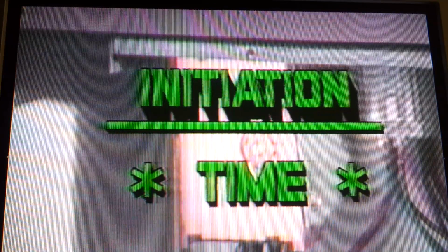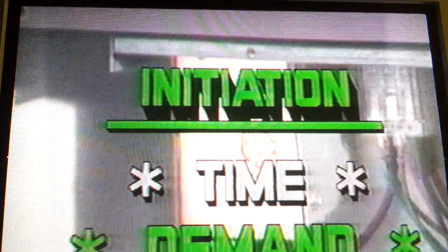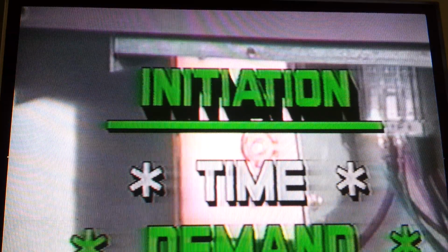The methods used for the initiation of a defrost cycle fall into two broad categories. The first type uses a timer which initiates on a predetermined time cycle. The timer initiates defrost every 30 to 90 minutes, as long as the coil is cold enough to support freezing. If the coil is above freezing temperatures, the timer skips the defrost cycle. The second method, control of defrost based on demand, attempts to measure the actual buildup of ice on the coil. Only when the coil is blocked is there a call for defrost.